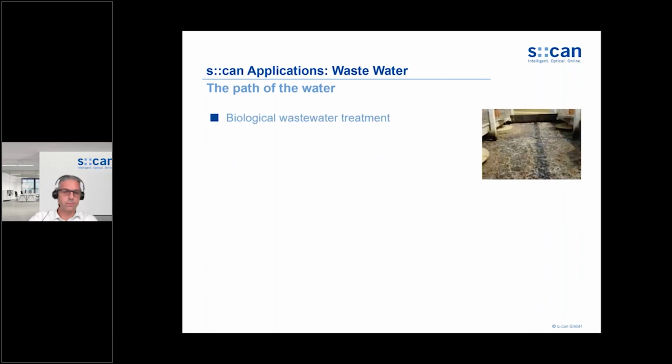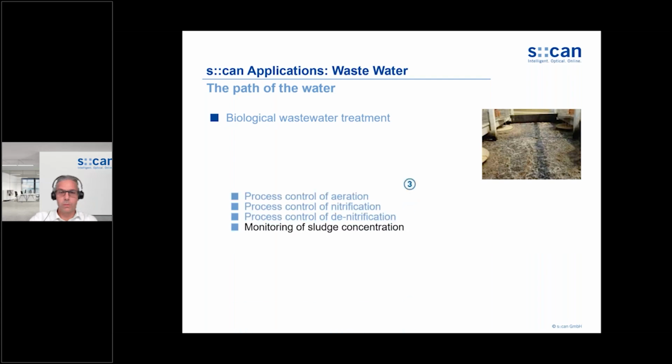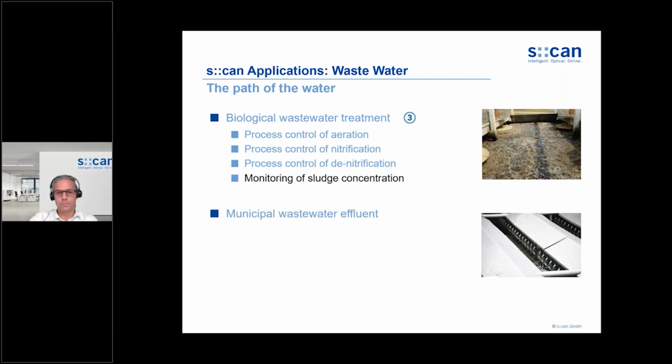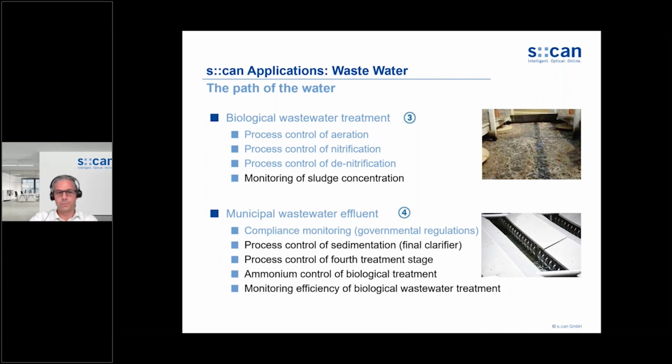Now the water goes to the biological wastewater treatment, and what we are doing here is controlling the process of the aeration, the nitrification, the denitrification, and we are monitoring the sludge concentration. In the effluent, the water is already cleaned. Compliance monitoring is a big point here. Government forces the wastewater treatment plants to monitor their effluent. Also, the process control of sedimentation taking place in the final clarifier, controlling the fourth treatment stage if present, the ammonium control of the biological treatment, and of course the efficiency of the complete biological wastewater treatment.